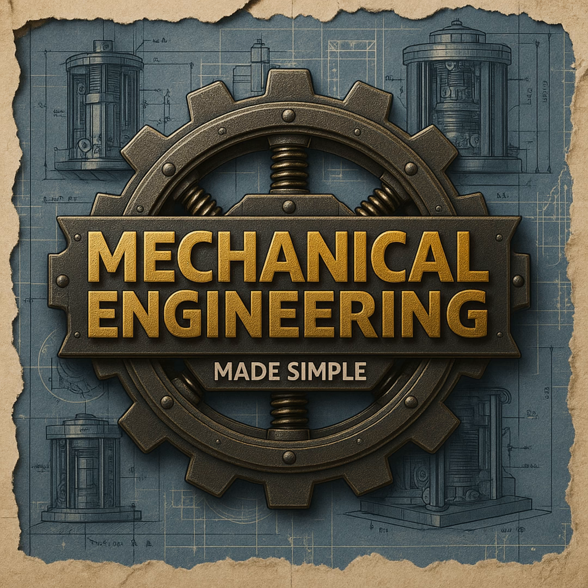Okay, moving through the rotary family, what about the sliding vane compressor? Okay, picture this. You have a rotor, but it's mounted eccentrically, off-center, inside a cylindrical housing. The rotor has slots, and in these slots are vanes that can slide in and out. As the rotor turns, centrifugal force throws the vanes outward, so they seal against the housing wall. Because the rotor is eccentric, this creates crescent-shaped pockets of air that get smaller as the rotor rotates, compressing the air. Where are these typically used? They're good general-purpose machines, often single-stage up to about 50 psig, or maybe staged up to 125 psig. And they're actually excellent for vacuum service, too, down to about 28 inches of mercury.